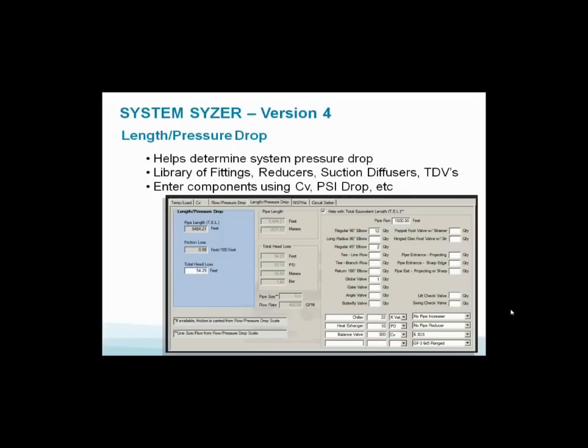Here's how we do this. I come in here and I fill in how many elbows do I have, how many T's, how many gate valves, butterfly valves, what's the length of my pipe actual runs, do I have a check valve, a triple duty valve, a chiller? All this is built into this table. You can plug in each one of those numbers, and you'll wind up left-hand side with total head loss required for your pump.